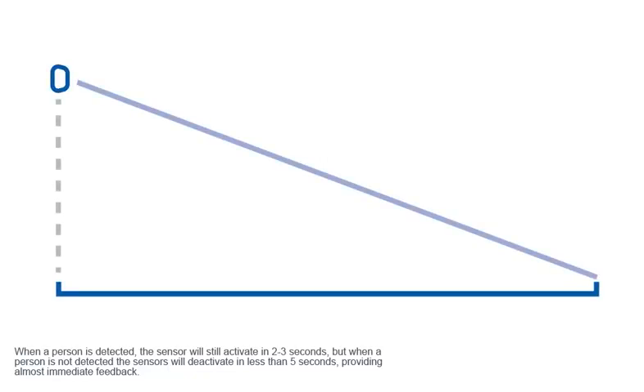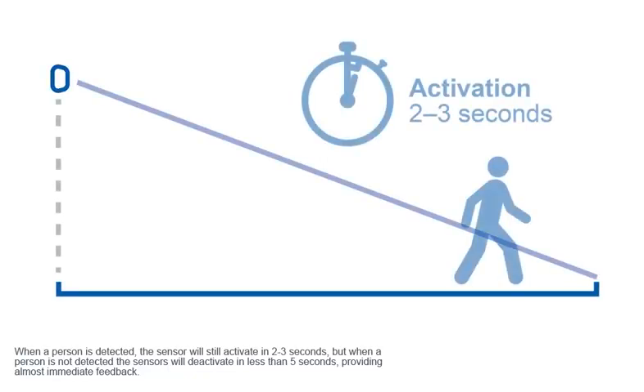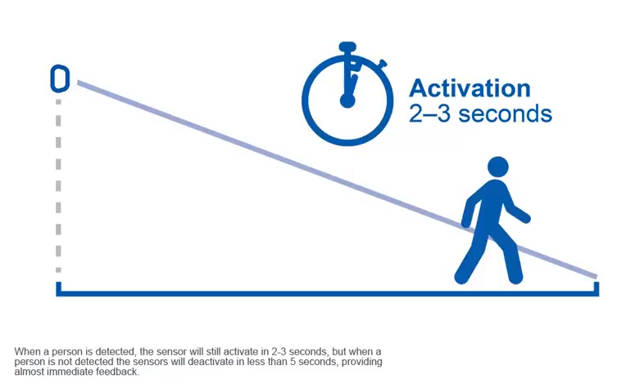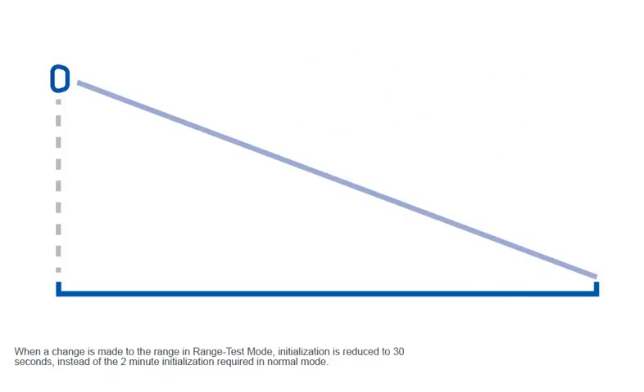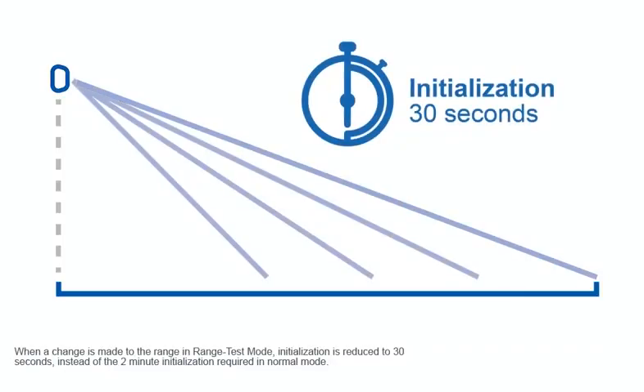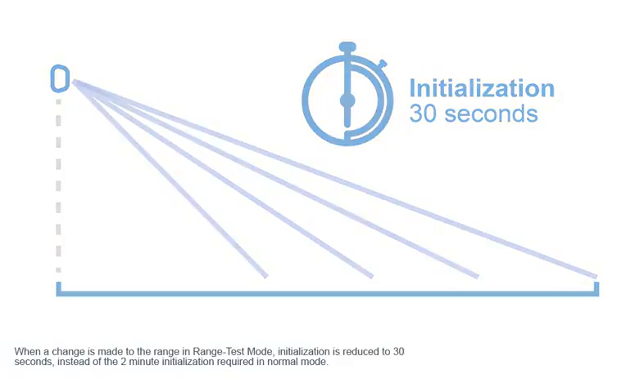When a person is detected, the sensor will still activate in 2-3 seconds, but when a person is not detected, the sensors will deactivate in less than 5 seconds, providing almost immediate feedback. When a change is made to the range in range test mode, initialization is reduced to 30 seconds, instead of the 2-minute initialization required in normal mode.